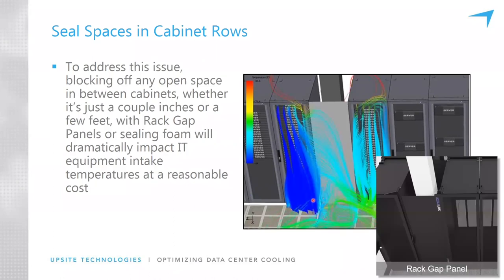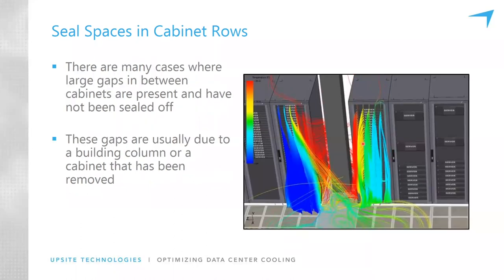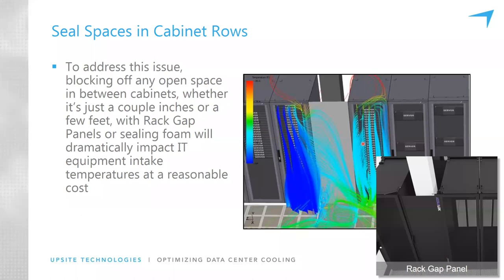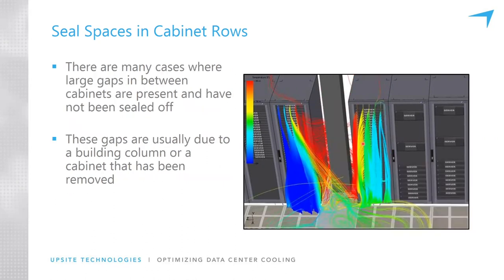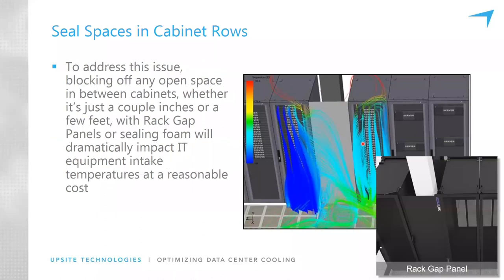But once that space is blocked, in this case with a rack gap panel, a screen type solution that attaches magnetically and is pulled out to block this space, now the cold air from the supply tiles can do its job and get to where it's needed. An important point to make here is that in both these models, there is the same amount of air coming out of the supply tiles at the same temperature. So just because you have cold supply air doesn't mean you're going to get rid of hot spots. Airflow management improvements, sealing those gaps, can really make a difference to that.